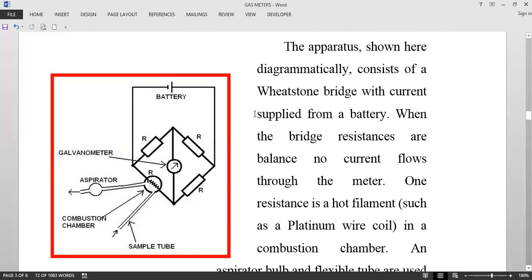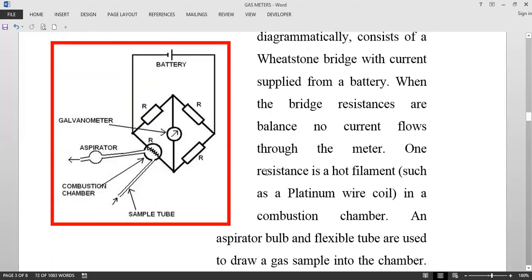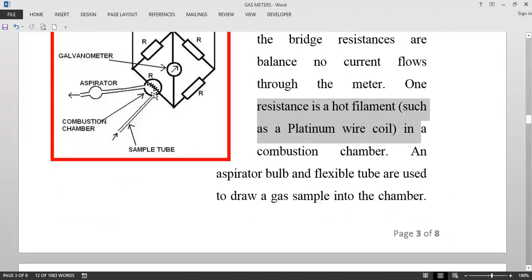The current is supplied from a battery. When the resistances are balanced, no current flows through the meter. One of the resistances is a hot filament — a platinum wire coil. There is also a combustion chamber where combustion actually takes place. An aspirator bulb and a flexible tube are used to draw a sample of air or gas into this combustion chamber.